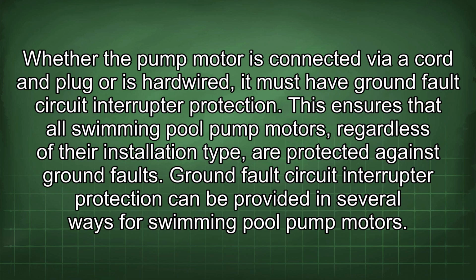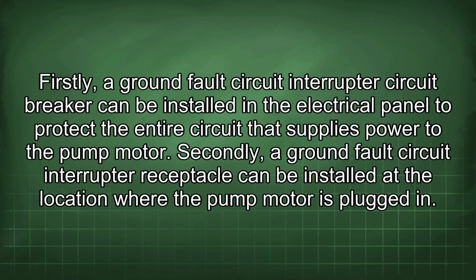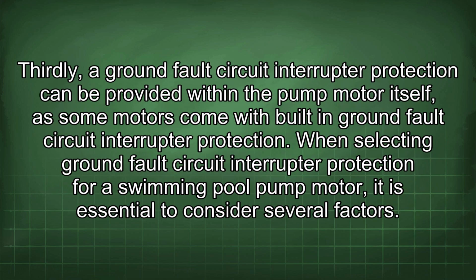Ground fault circuit interrupter protection can be provided in several ways for swimming pool pump motors. Firstly, a ground fault circuit interrupter circuit breaker can be installed in the electrical panel to protect the entire circuit that supplies power to the pump motor. Secondly, a ground fault circuit interrupter receptacle can be installed at the location where the pump motor is plugged in. Thirdly, ground fault circuit interrupter protection can be provided within the pump motor itself, as some motors come with built-in ground fault circuit interrupter protection.